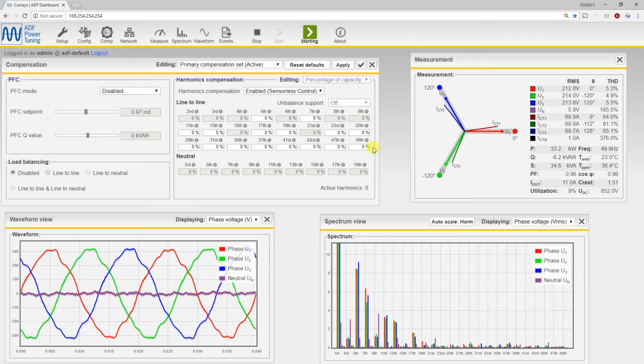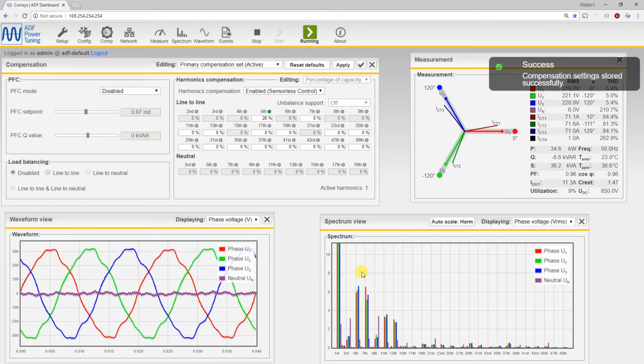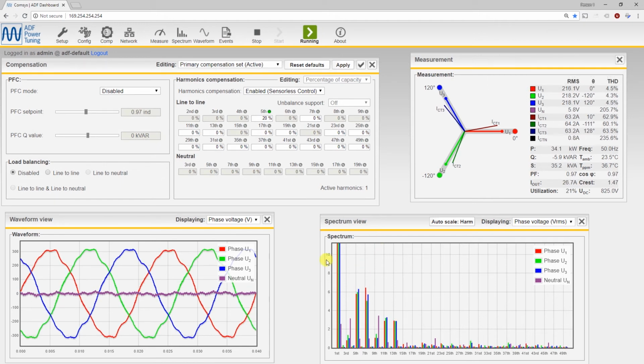And with the filter started now, we can start to add some values to the compensation, and we can see how the filter reacts. Right now we have on the 5th harmonic 8 volt. We typically start with a relatively small value on the sensorless control compensation. So we start with 20% on the 5th harmonic. 20% now means 24 amps that we can give out to reduce the voltage distortion on the 5th harmonic. If we apply the setting now, we see the 5th harmonic is dropping down. When we see that it's dropping down, then we're fine to increase the value a little bit further.